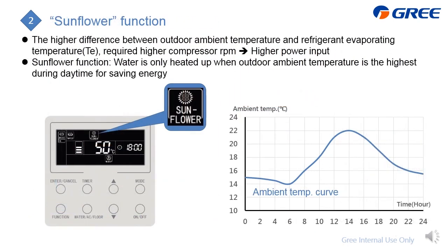Next is the sunflower function. What is the sunflower? It is that according to the daylight temperature change, the system will also record a curve just like this. And this is the picture. This graph here is the hour, and here is the outdoor ambient temperature. The system can automatically record the outdoor ambient temperature according to the different time. And then when you select to activate this sunflower function, the compressor is only heating up the domestic hot water within this area. That means we will find almost the highest zone during one day to heat up the domestic hot water, which can improve the system efficiency.